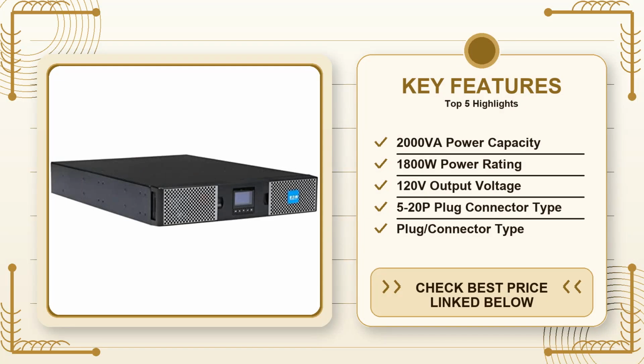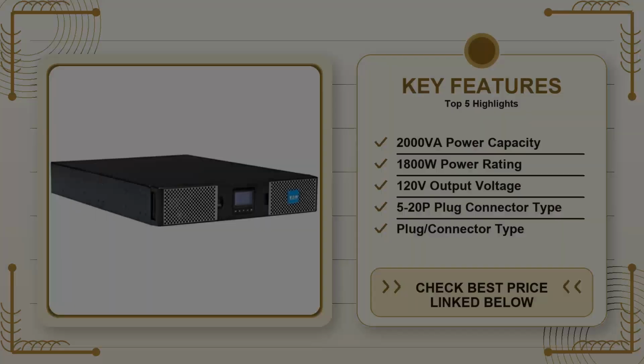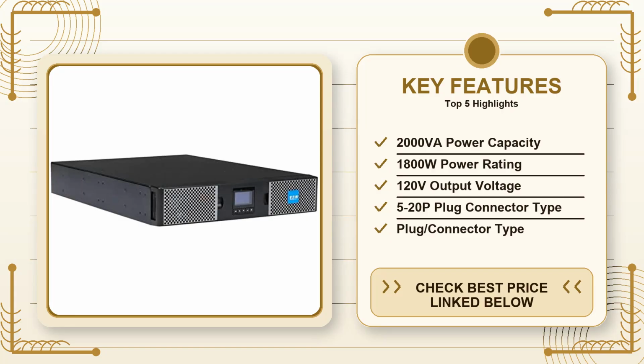Now let's look at the real-world performance that matters after you've got it plugged in. The 9PX's online double conversion design promises true sine wave output, which is essential if you're running sensitive electronics such as a laser cutter controller or a high-precision CNC machine. Those devices often have internal power supplies that expect clean, stable input. A cheap or poorly regulated UPS can cause them to misbehave or shut down unexpectedly.